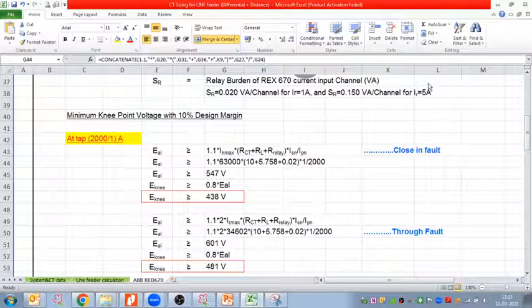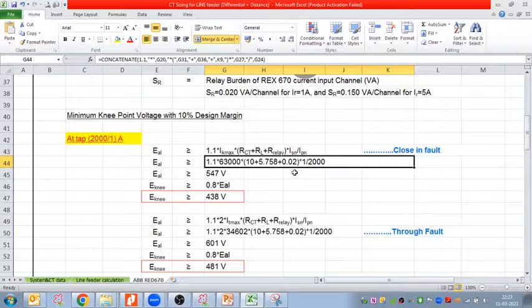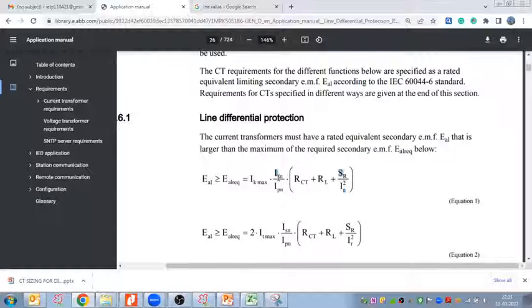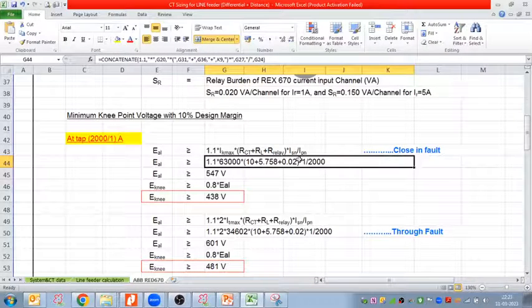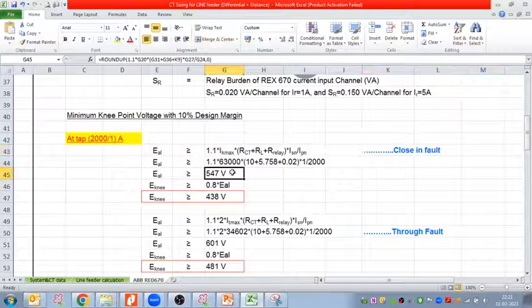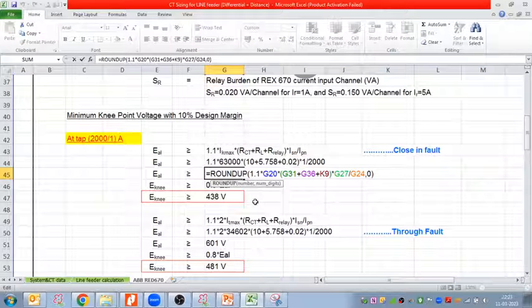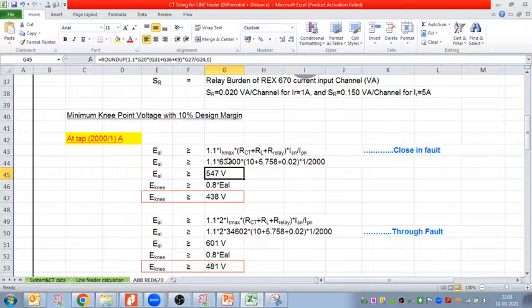Okay. So 10 plus 5.758 lead plus your relay resistance, multiplied by ISN, this much, 1 divided by 2000. So this much into 1 divided by 2000. How much value is coming for the close-in fault conditions? Eal is 547. I just multiplied all this. So solve this, it will come 547 voltage, right?